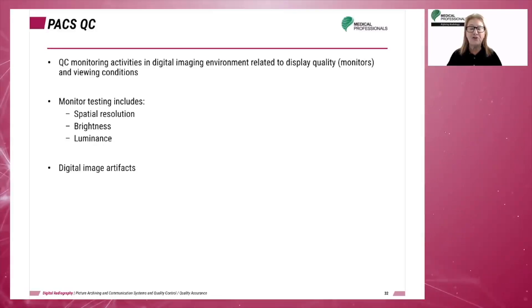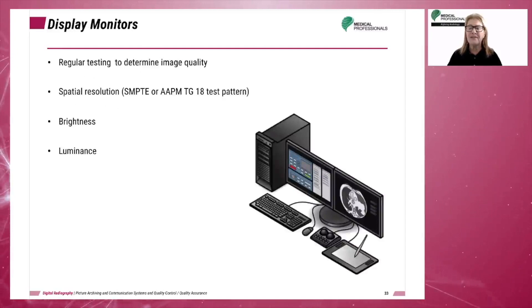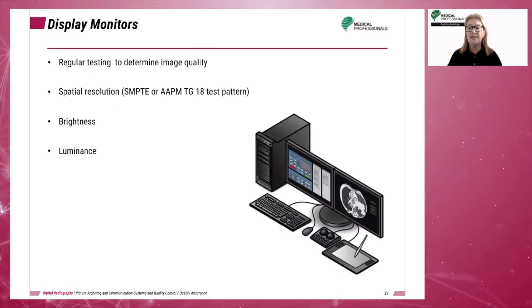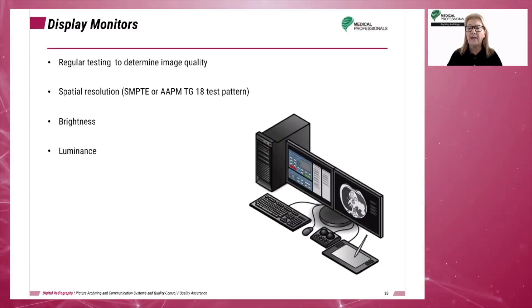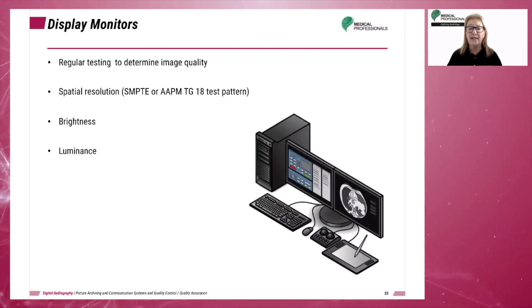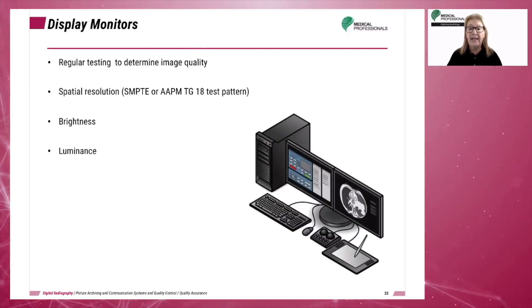In addition to the quality parameters previously discussed, digital imaging QC activities are also related to the PACS, workstation, and reading monitors, and to image artifacts. Both the ACR and the AAPM recommend regular QC testing; however, they differ in their timelines. The ACR recommends testing at least monthly, while the AAPM recommends daily and monthly procedures carried out by the radiographer and annual tests performed by the medical physicist.